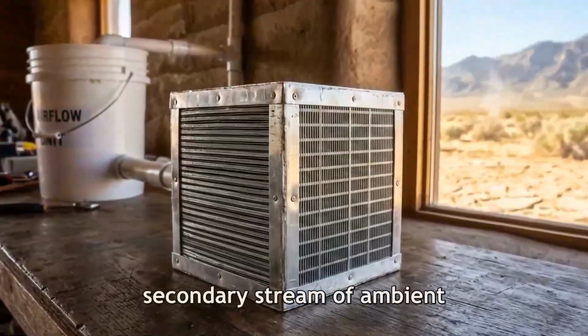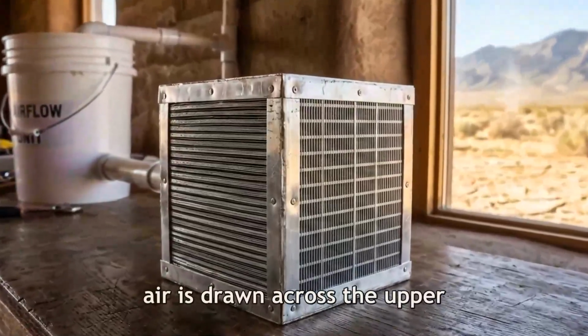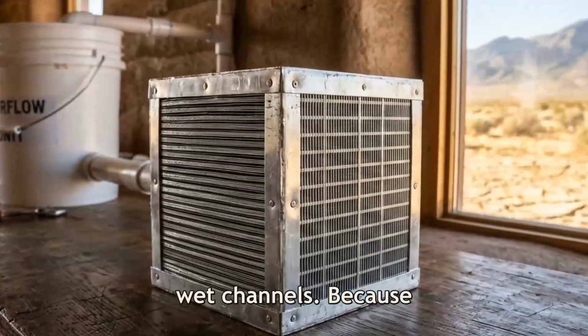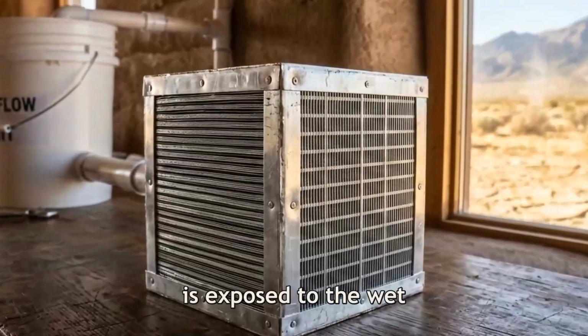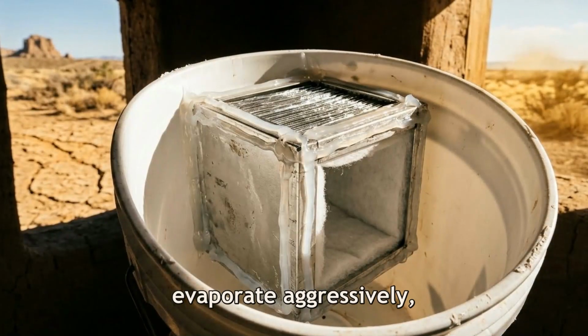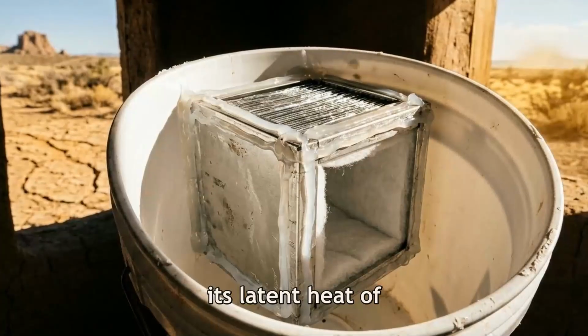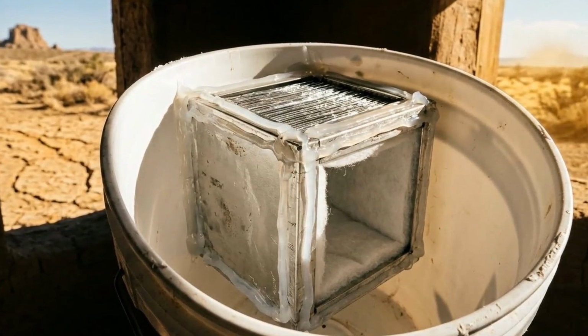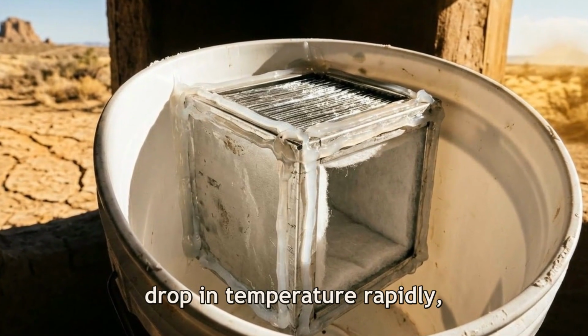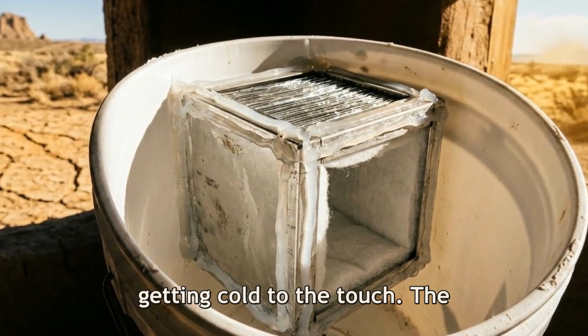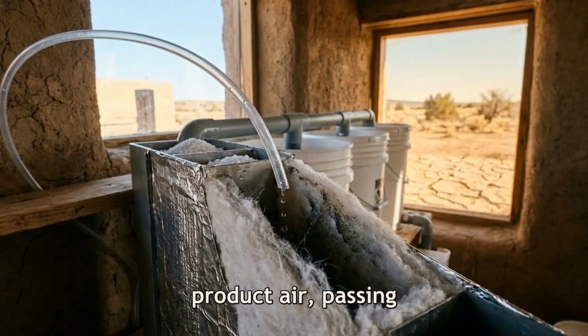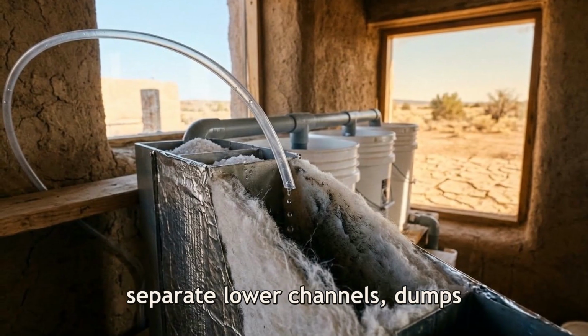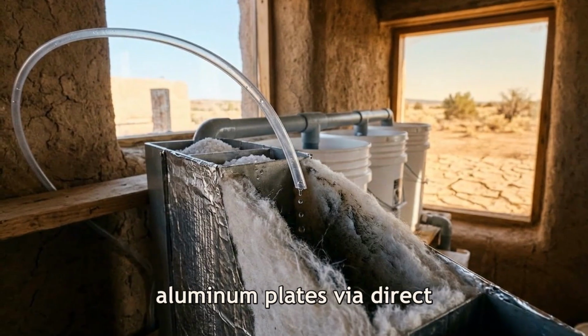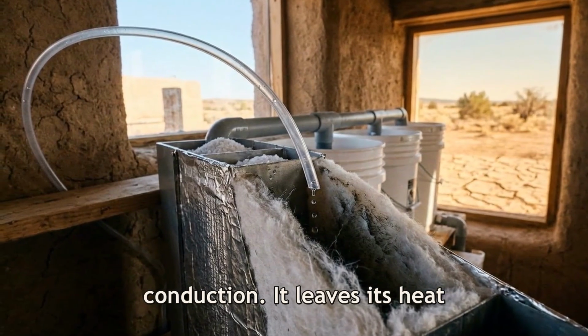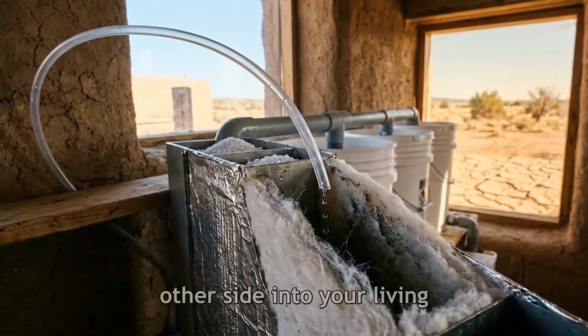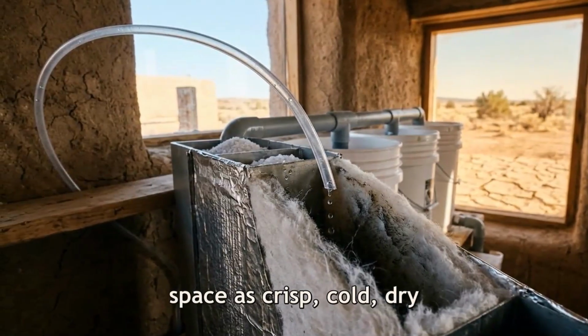At the same time, a secondary stream of ambient air is drawn across the upper wet channels. Because the air in the upper channels is exposed to the wet wick, the water begins to evaporate aggressively, absorbing its latent heat of vaporization directly from the aluminum plates. The aluminum plates drop in temperature rapidly, getting cold to the touch. The product air, passing through the completely separate lower channels, dumps its heat into these freezing aluminum plates via direct conduction. It leaves its heat behind and exits the other side into your living space as crisp, cold, dry air.